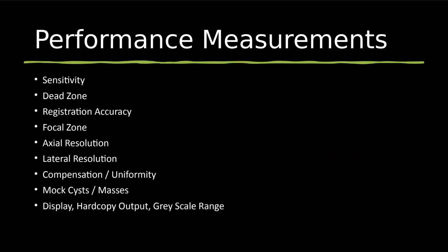And usually with these phantoms, we're looking for specific things. We're evaluating specific measurements. We're looking at the sensitivity of our sound source. We're looking for evaluation of the dead zone, the focal zone. We're looking for registration accuracy, which is again, how accurate can we identify individual structures on our picture. We're looking at axial and lateral resolution, which we'll talk a little bit more about, and we already know a lot about them. Also compensation and uniformity, so our grayscale and our TGC, our gain and our TGC.